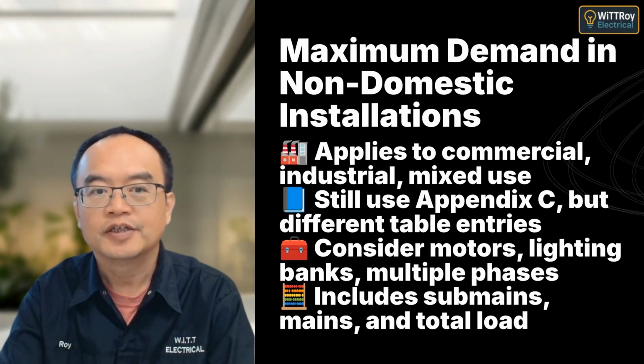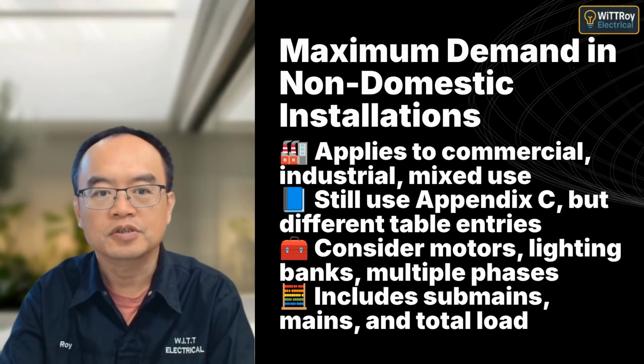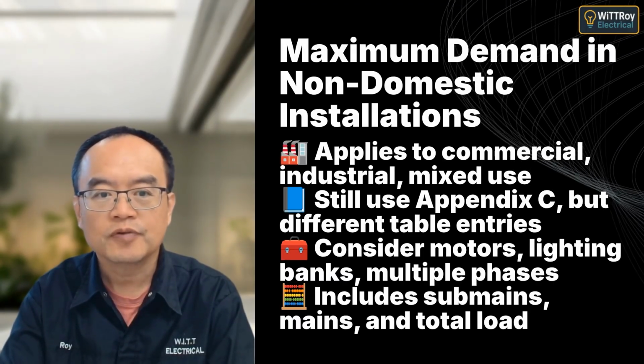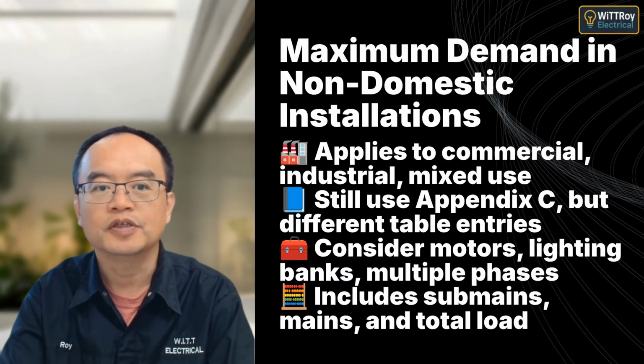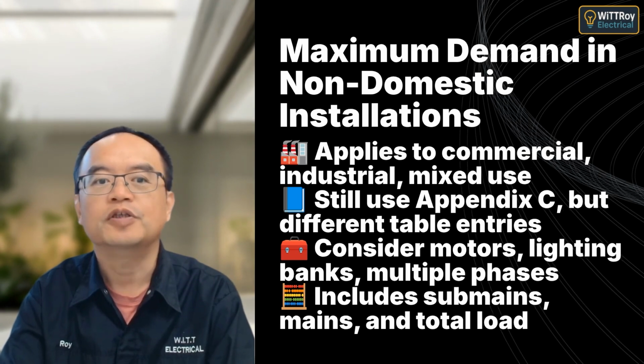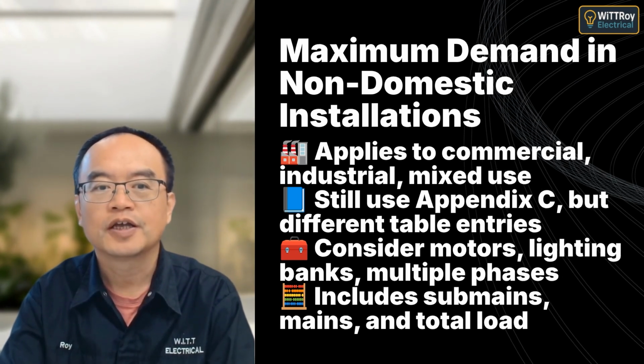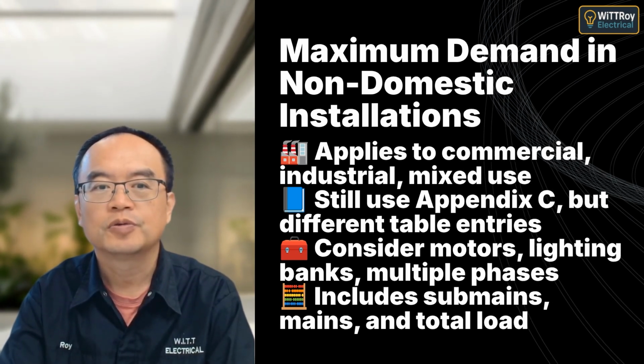In non-domestic sites, maximum demand includes motors, groups of lighting circuits, and three-phase loads. You still apply demand factors, but check the right rows in Appendix C. This helps you calculate total installation loading for switchboards and feeders.